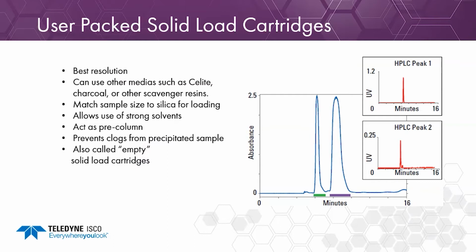If you choose the solid option, it's assuming that you've already put your sample cartridge on there, and it's going to bypass flow to the cartridge automatically after the equilibration step. So it's going to continue right away. Those are two key things to realize there. If you do liquid, it's going to wait for the equilibration to get done and then ask you to inject the sample.